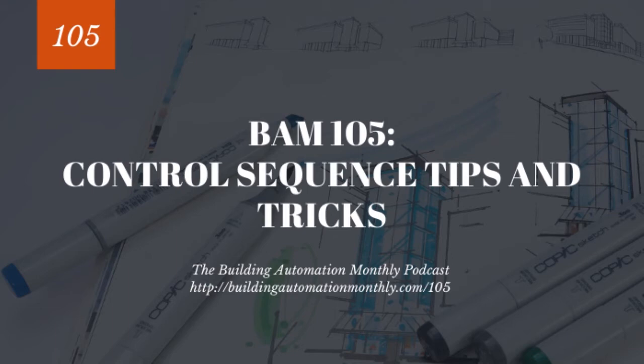If you go and, for example, let's say this right here. You have a sequence of operations, and the first thing it does is look at the VAV box position before it turns on the air handler, because you don't want all the VAV boxes closed before the air handler turns on. Now, I'm completely making this up as I go, but this sequence will still prove a point. You won't see a whole lot of ones where you have to have all of the VAV boxes open, because those are normally set, but go with me on this. So you have this sequence that says, I've got to have all these VAV boxes open, or at least at minimum position, before I enable my air handler.